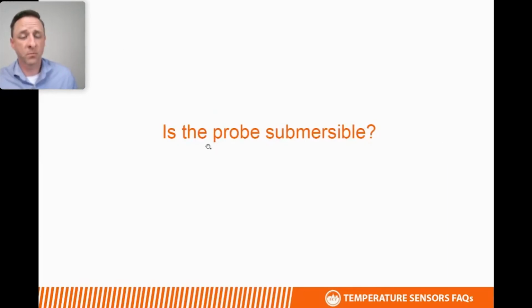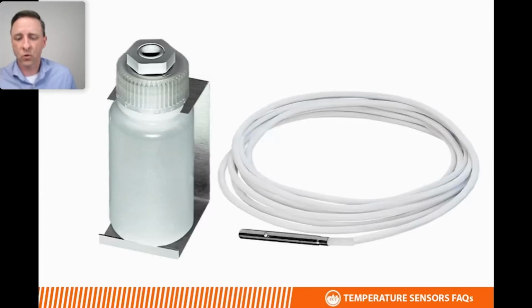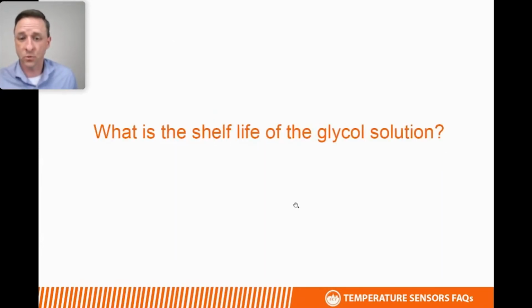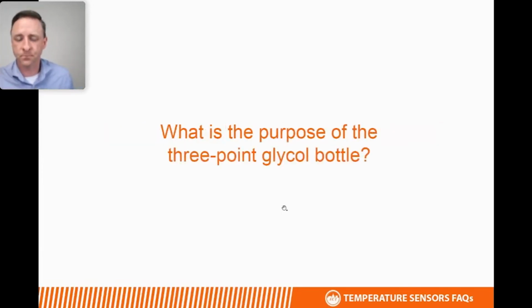Is the probe submersible? Yes, like the other probes, and I'll go back to this slide, the tip of the probe is submersible. The entire length of the probe is not. So when installing the probe into the glycol bottle, ensure that just the tip of the probe is in the solution. What's the shelf life of the glycol solution? And I believe that the shelf life for that is, let me look at my cheat sheet here. It's 2 years if stored at room temperature and outside of direct UV light or sunlight.